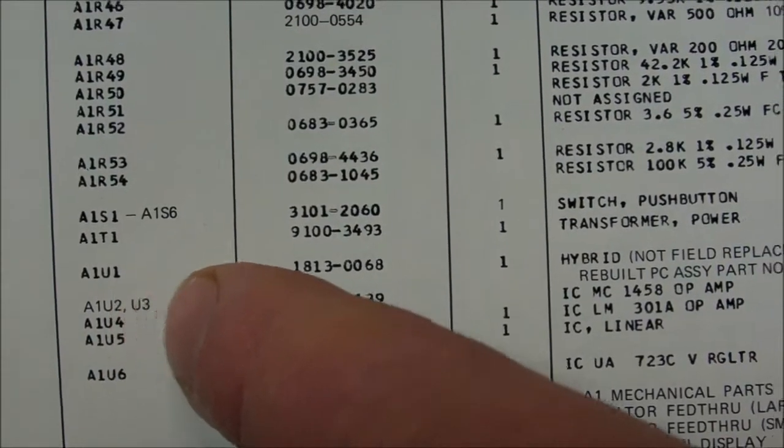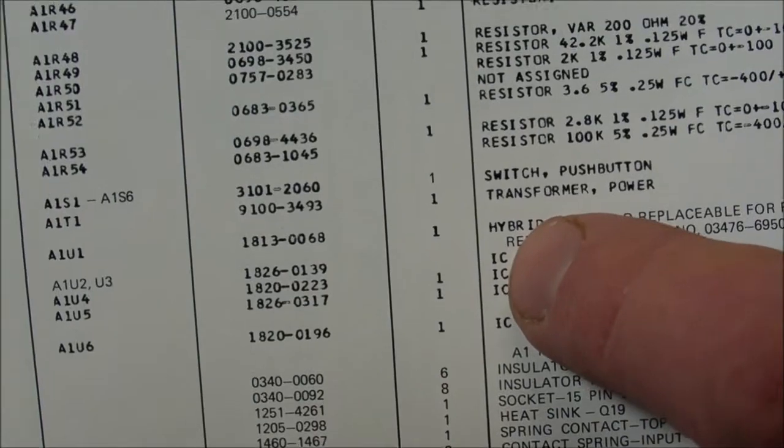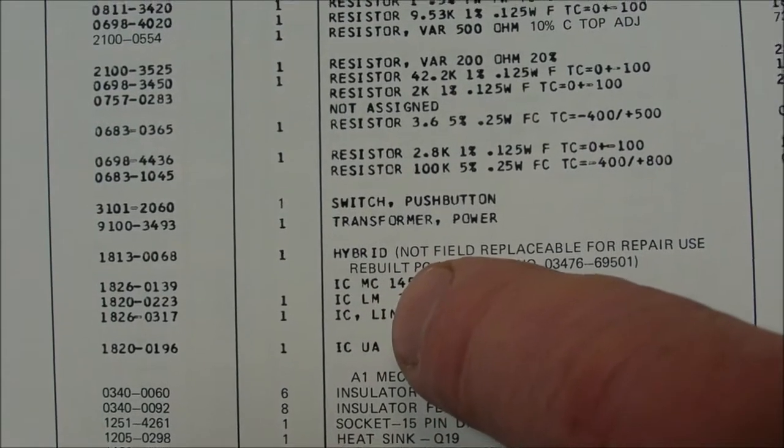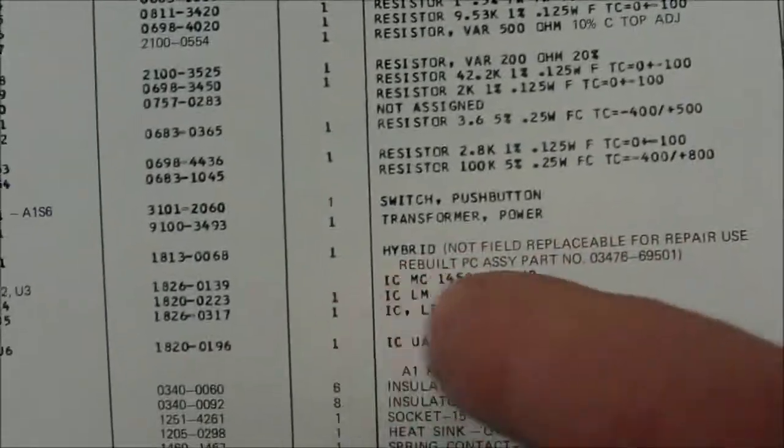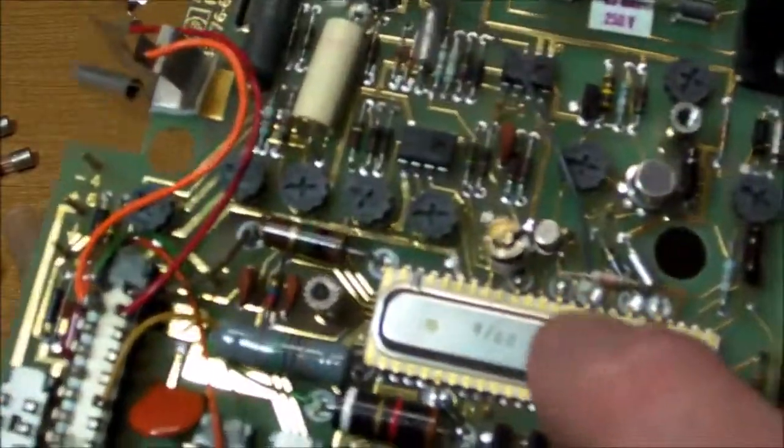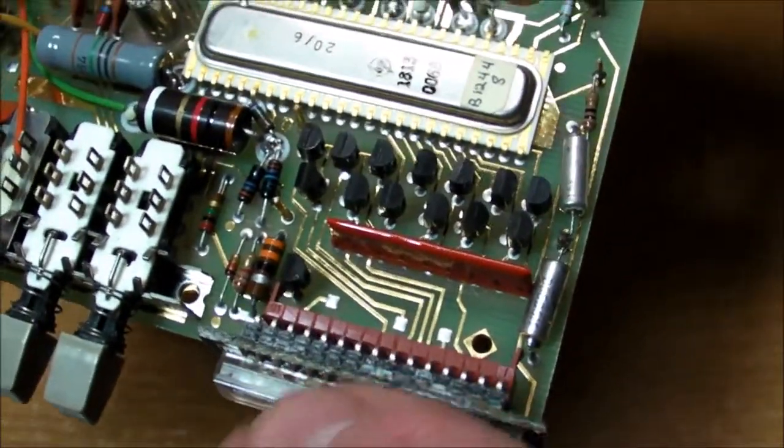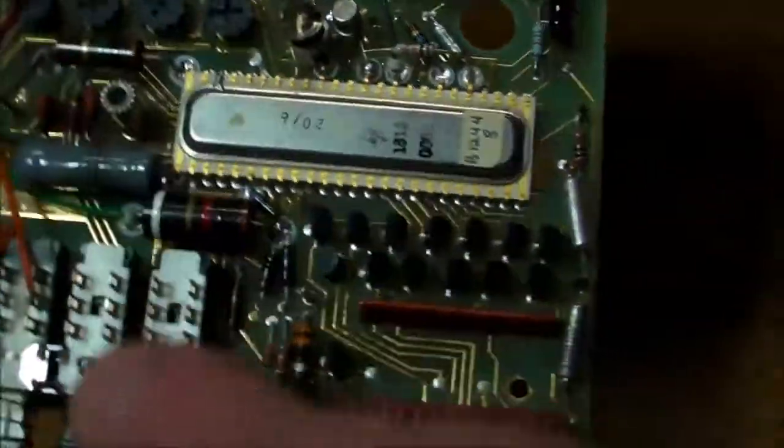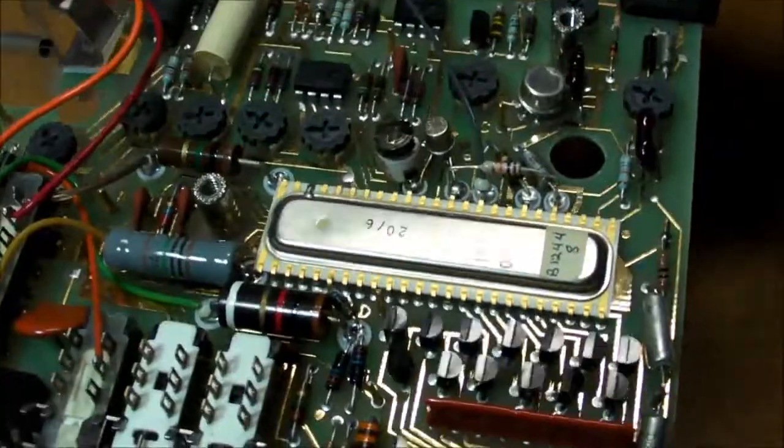And so let's look at the list of parts. U1, there's the HP part number and a hybrid, so it's basically just an NMOS hybrid IC, not field replaceable. For repair, use rebuilt printed circuit board assembly, part number blah blah blah. So this thing, if this thing is busted at all when it comes to the LED display with some of the segments being out, then it's technically not field replaceable.